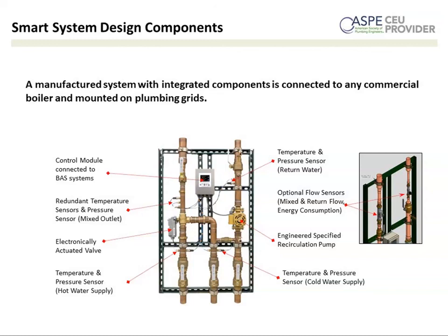And then, a couple things that aren't really pointed out, you've got obviously isolation valves throughout the unit, which makes it easy to get at components. There are check valves throughout the unit to make sure we mitigate the issues of cross flow. In this particular unit, you're simply modulating a three-way ball valve. So it's a very simple style valve, which makes it very easy for repair. You can see the actuator on the left-hand side, the silver device, and that has the manual override we talked about earlier. So in a lot of cases, the actuator is separate from the valve and makes access and maintenance very easy.